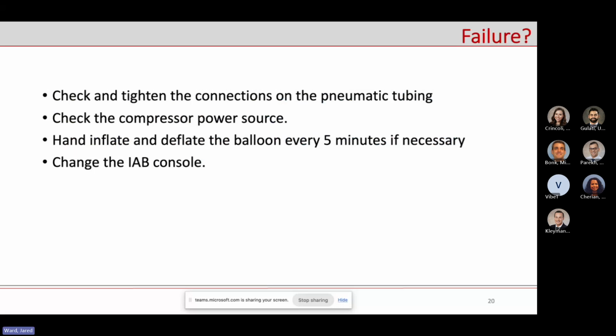Generally, the most common thing with the balloon pump, if something's not working, is you just need to run the tubing. There's in general a disconnect somewhere in the tubing if the balloon isn't capturing, if the waveforms aren't working, if the waveforms are off and funky, it's because something isn't connected. And then the other thing would just be to make sure that it's hooked up to a power source, and that the battery hasn't run out because it just sat down in the cath lab but wasn't charging.